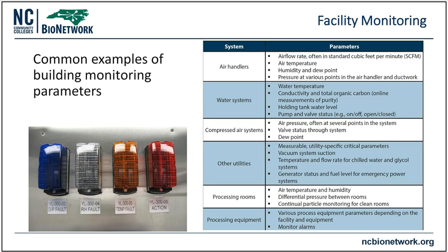Building monitoring focuses on everything. At the top of this table you'll see air handlers listed -- not optional, but something we must monitor: flow rates, how fast air is pumped into the room, how fast it's sucked out, what the filters are like, the temperature of the air, and the humidity of the rooms. These things have to be tracked and logged over time to make sure the building and room integrity still exists the way we intended.